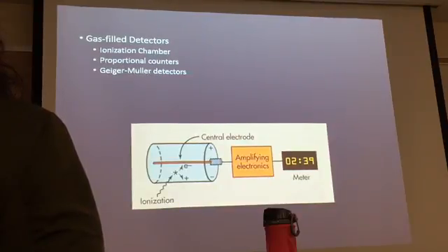Okay? You increase the voltage a little bit, and then you get into the area of the ion chambers, the ionization chamber. You know you have some sensitivity, somewhat accurate. So you can measure, you can go down to one millirad. That's how sensitive they are. And the exposure times can be very short.